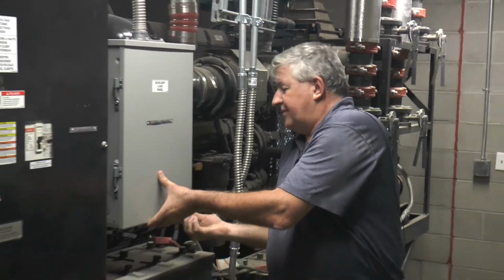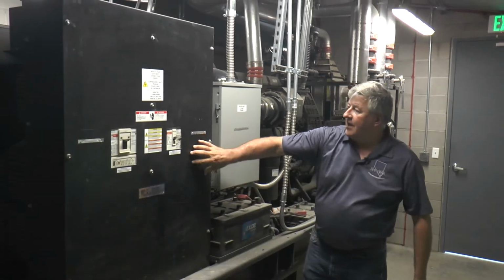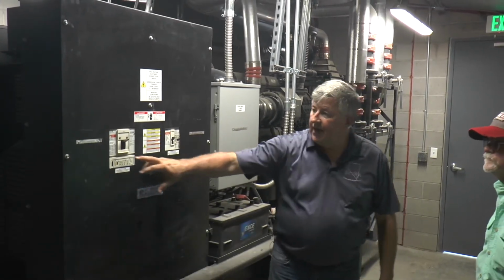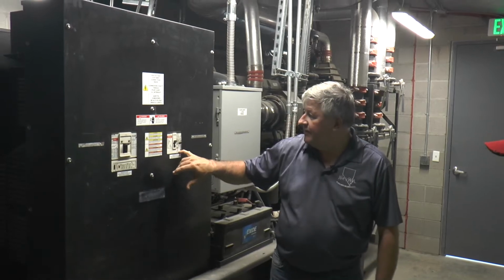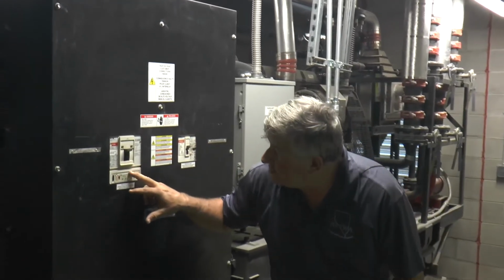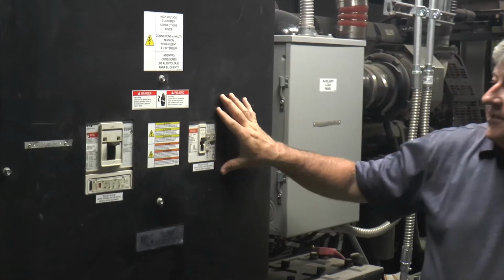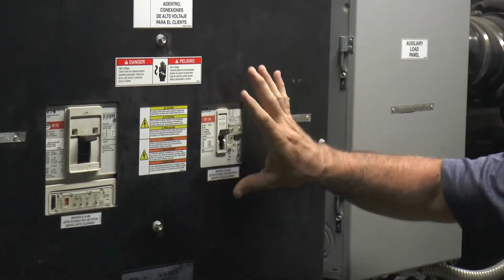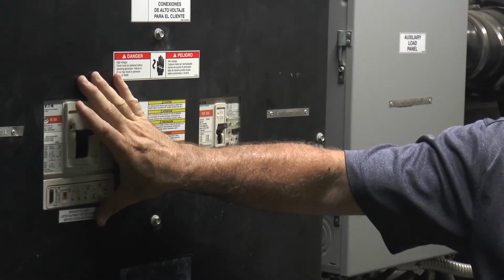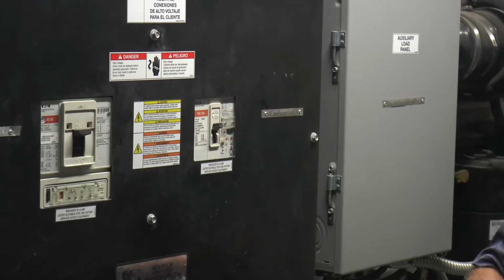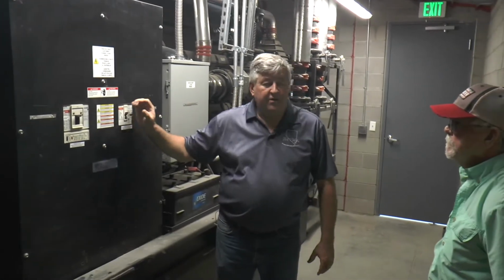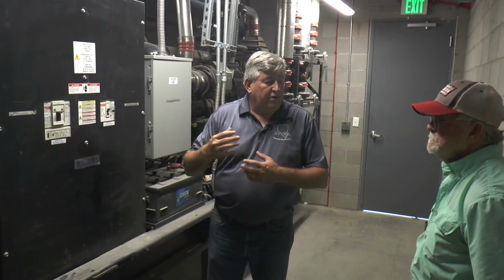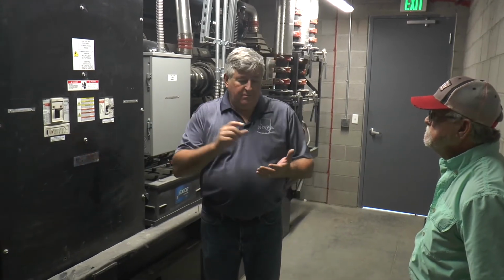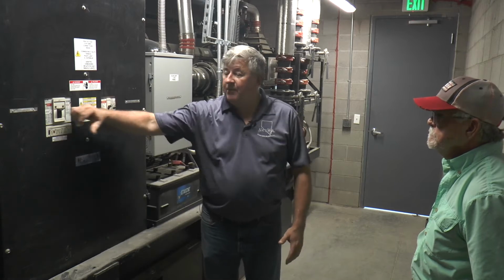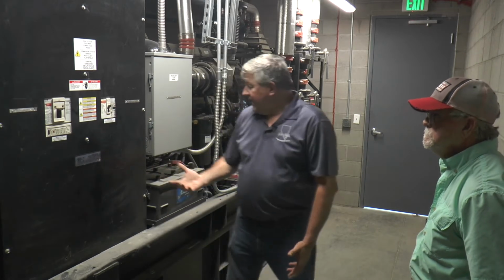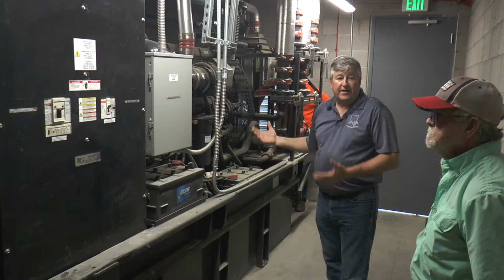This side of the generator set also keeps ATS1 and ATS2. ATS1 is a little 150 amp. ATS2, I believe, is a little 400 amp. This one's feeding all your egress lighting. This one is feeding all the elevators. When you're doing your inspection, verify all the breakers are in the on position. When you're done with your inspection, last thing I do, make sure the key's in auto and all the breakers are closed. That's basically it for your service and inspection on this side of the engine.